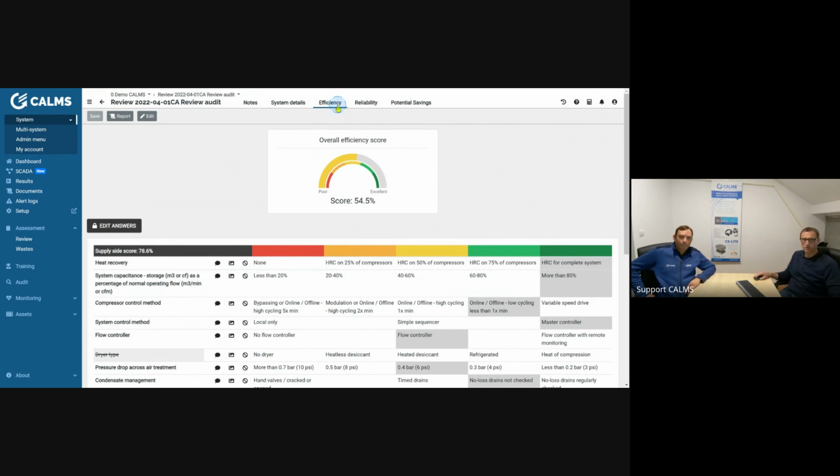So I would like to get also the other data like efficiency. Yeah. So we already did in the compressor room. You have heat recovery in all compressors, which is very good. Yeah, that's true, except on the new one. But it's coming. I asked for it. It's in the budget. It's not connected, so we will put it like it is now, and this is the improvement when you will actually receive the heat recovery cooler for this one.